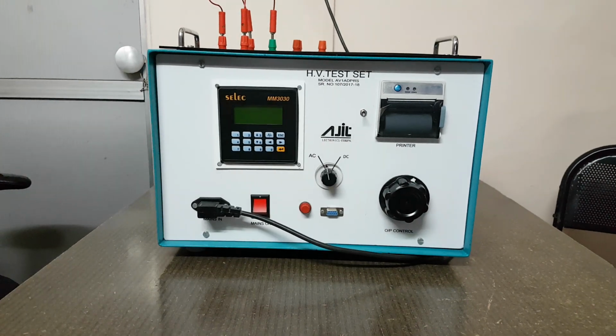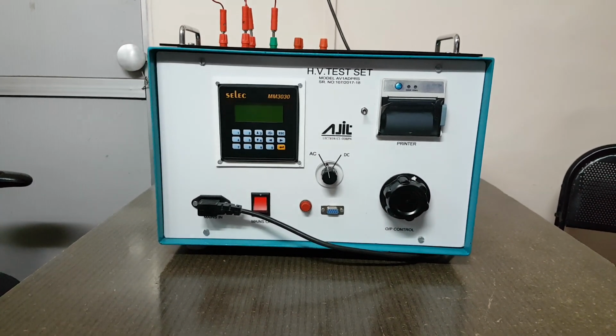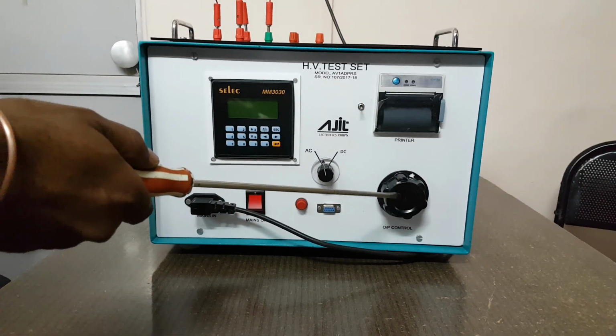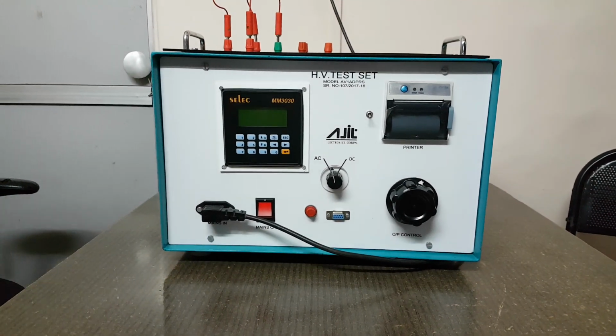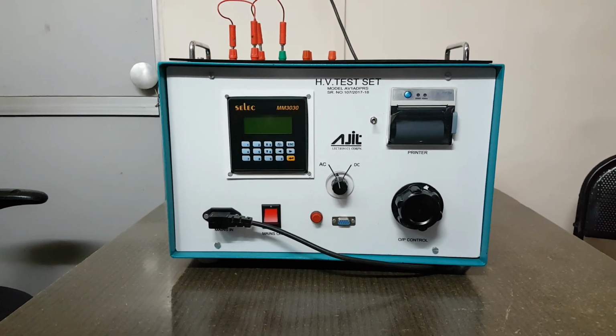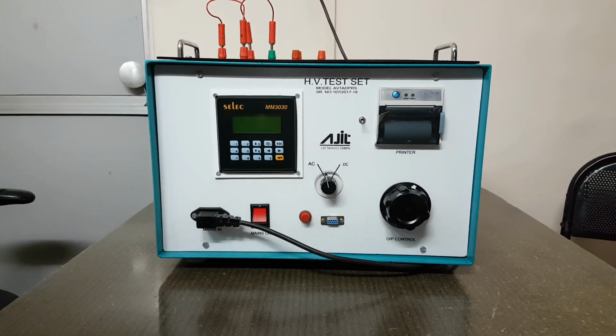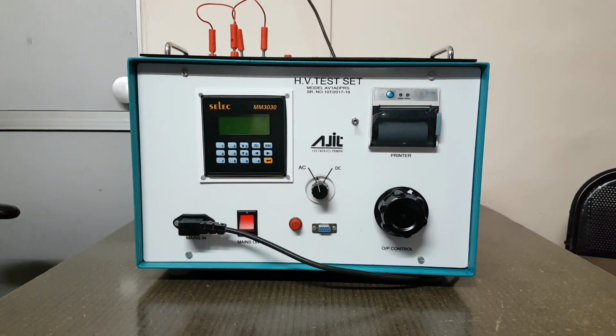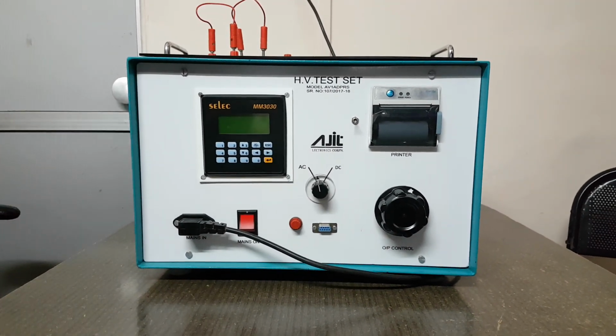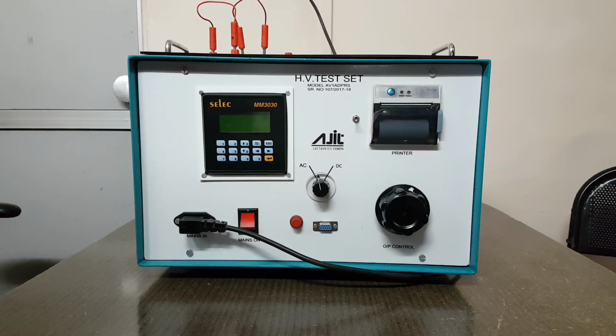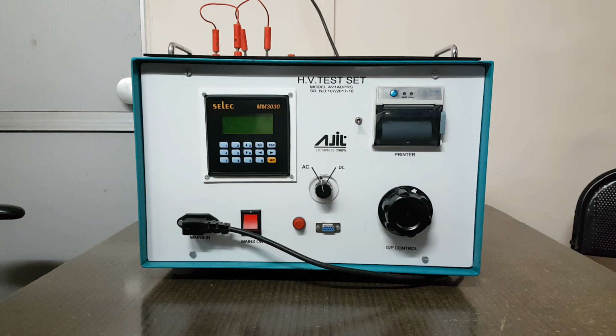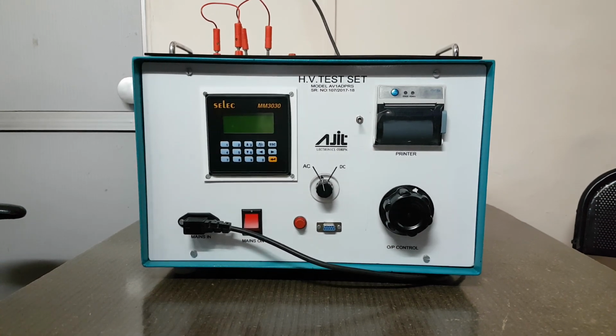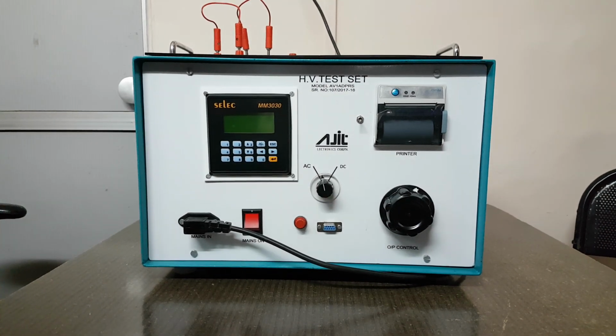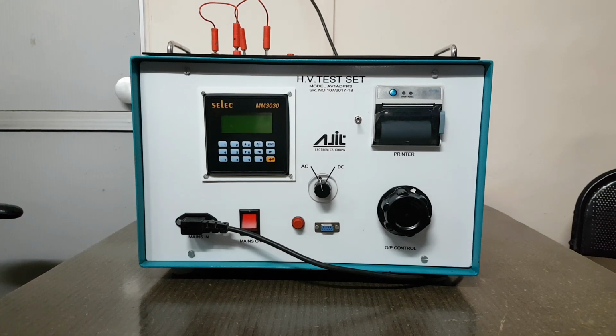The instrument has one more interlock, called the zero start interlock. That means unless this voltage controller is at zero position, the instrument will not initiate the high voltage. Now we will switch on the instrument once again because the electrical earthing is connected properly, the chamber door interlock is closed properly, and the dimmerstat or voltage controller is at zero position. All three interlocks are now intact. So let's switch on the instrument.